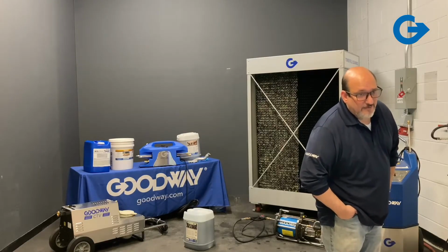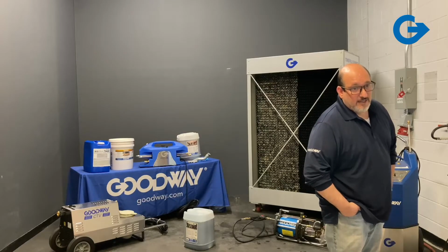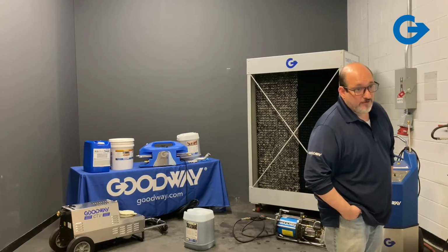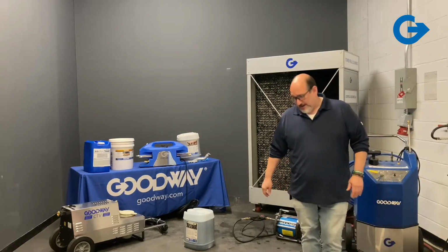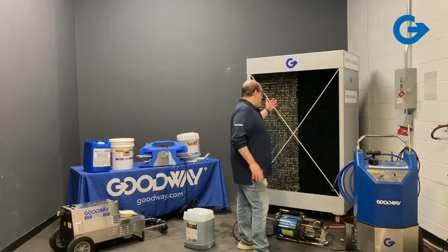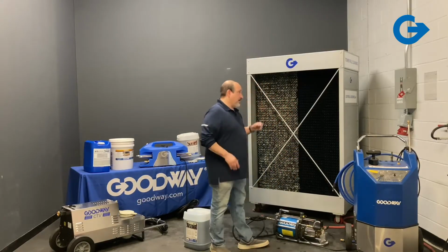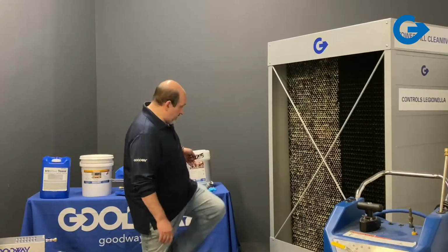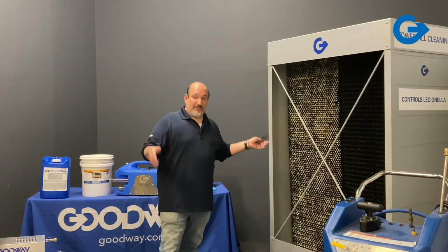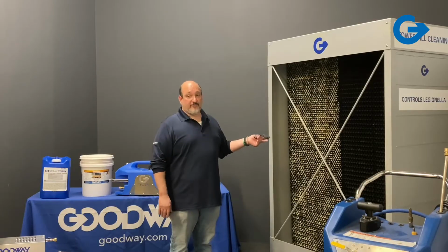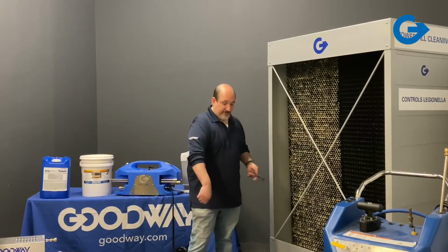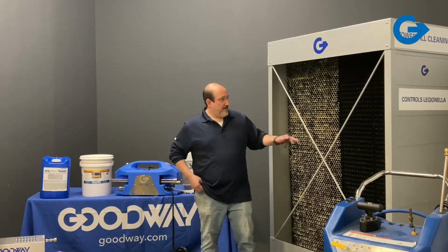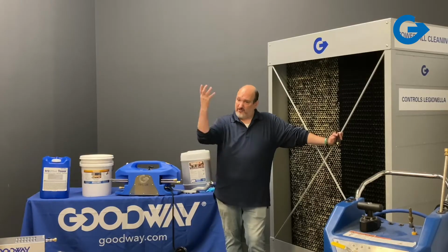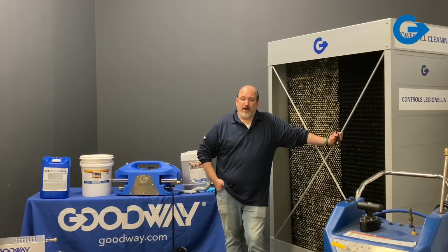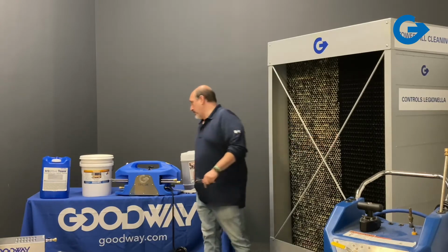Is it easier to clean hanging fill sheets than stacked block fill sheets like you'd see in a counterflow tower? How would you clean block fill with your machine in a counterflow style tower? Often you'd have sheets of fill kind of pancaked together inside. What you'd do is clean the inside surface, and if it's really thick with scale or biological buildup, you'd use the same machine and clean the inside as well—just take the gun inside with you and spray it down. Now if you're talking about a tower where the fill is on top and it's sort of raining down, that's something you probably wouldn't use one of the machines for cleaning the fill.